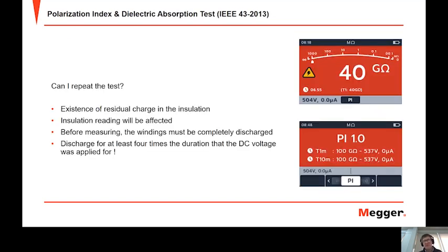So one question that comes up occasionally, maybe in the middle of a PI test, this test has to stop for some reason, and then I've seen customers repeat the test immediately. Is that a good thing to do? And the answer is no. If you've run a PI test for, say, 6 minutes and then had to stop the test for some reason, then there will be a residual charge within the insulation. And that means that when we run the PI test again, we will get skewed readings.